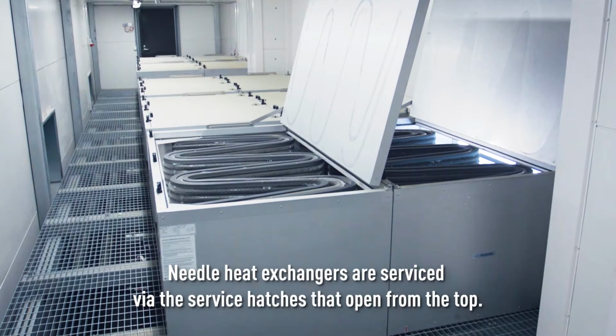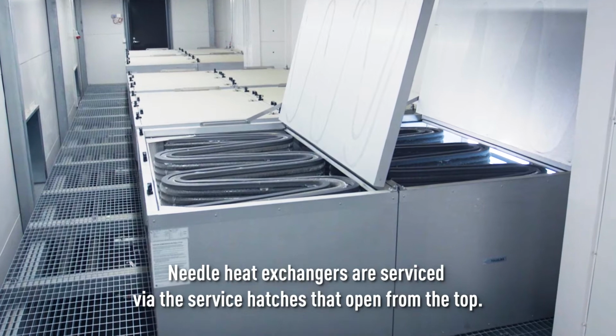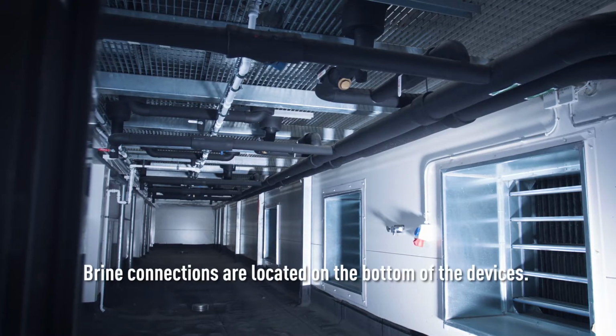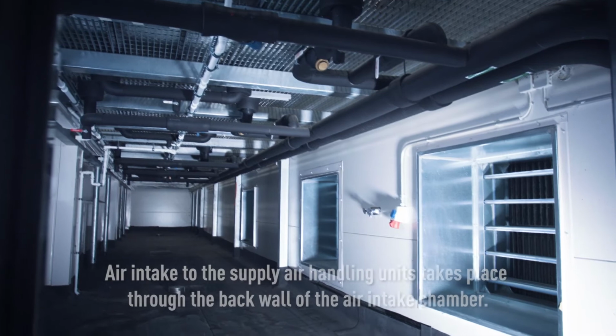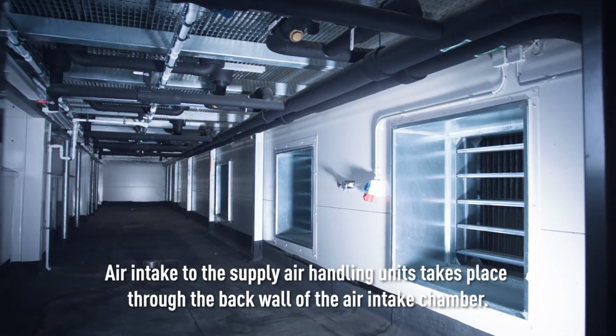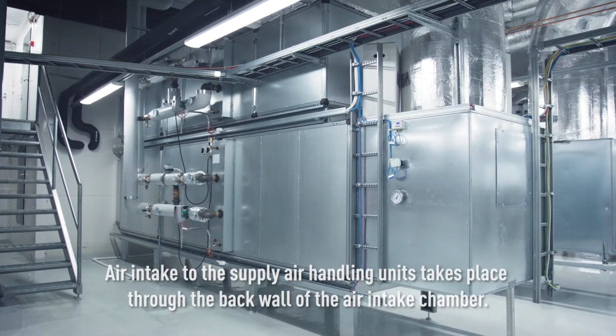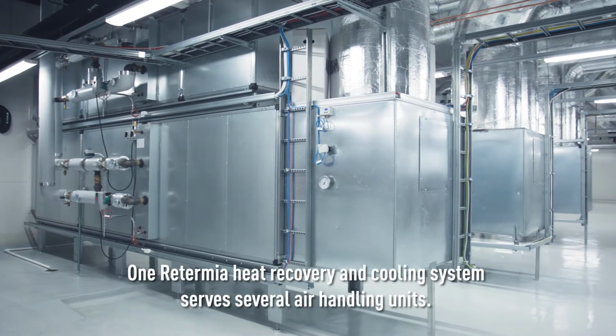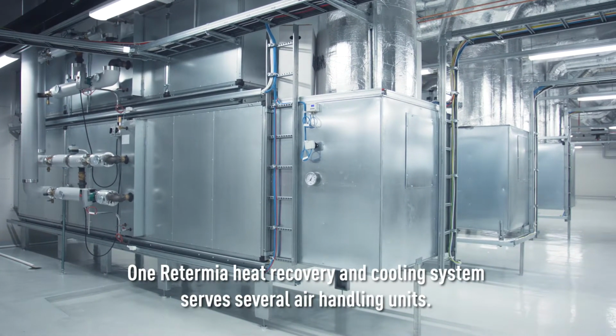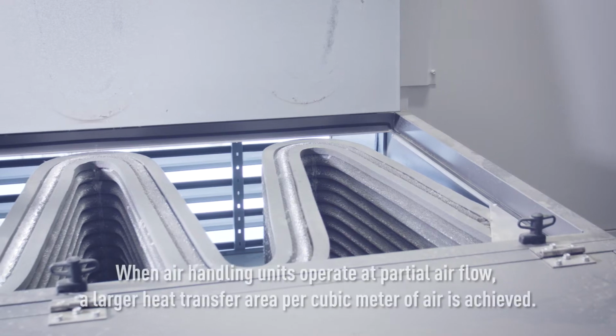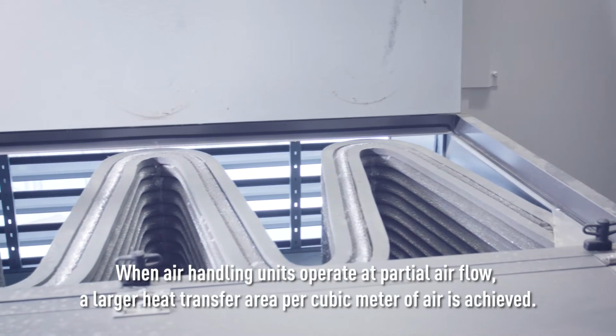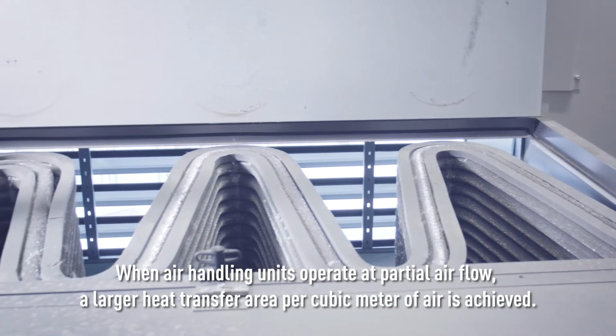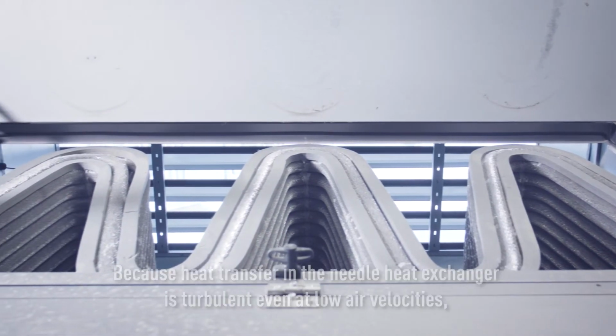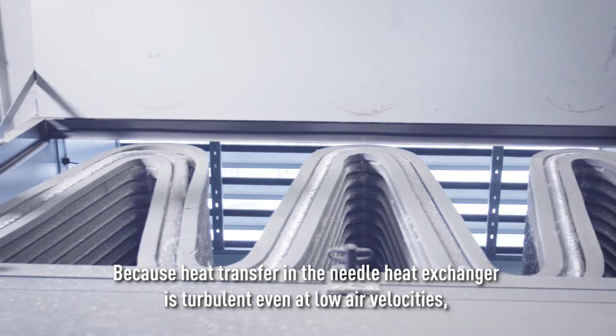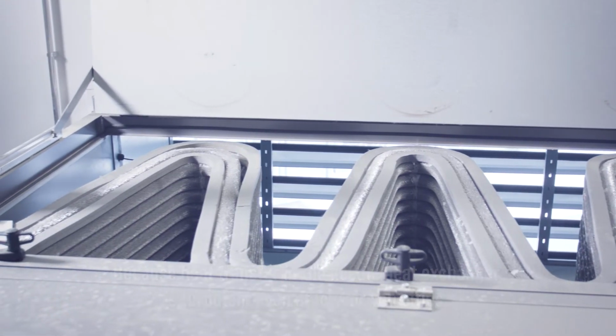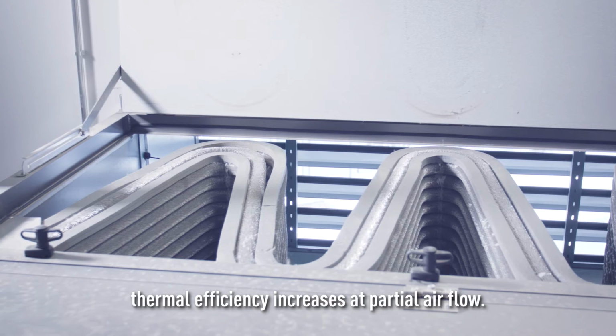Needle heat exchangers are serviced via the service hatches that open from the top. Brine connections are located on the bottom of the devices. Air intake to the supply air handling units takes place through the back wall of the air intake chamber. One Retermia heat recovery and cooling system serves several air handling units. When air handling units operate at partial airflow, a larger heat transfer area per cubic meter of air is achieved. Because heat transfer in the needle heat exchanger is turbulent even at low air velocities, thermal efficiency increases at partial airflow.